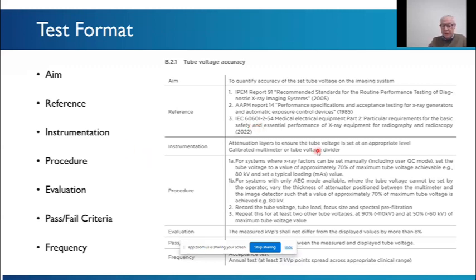Then any instrumentation. So what you would need to do the test. This test is the tube voltage accuracy. So you need a multimeter or kV divider and some attenuation. The procedure, which is how you do it in hopefully easy to read steps. And then how you evaluate. So you just check your measured kVs against the displayed values in this test, for example. And then any pass-fail criteria that you need to apply, and the frequency at which you do the test. So it could be an acceptance test or annual or constancy test, for example.